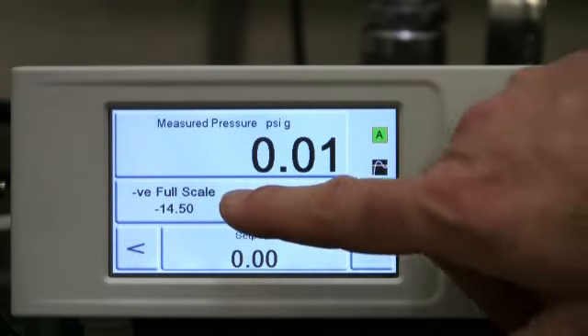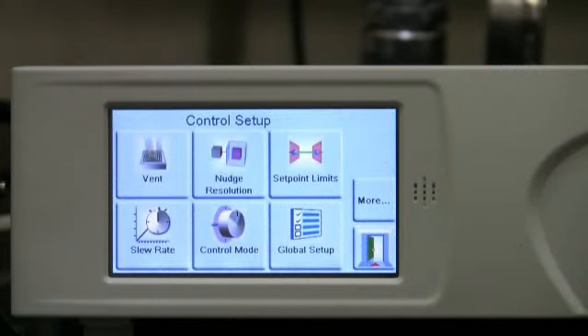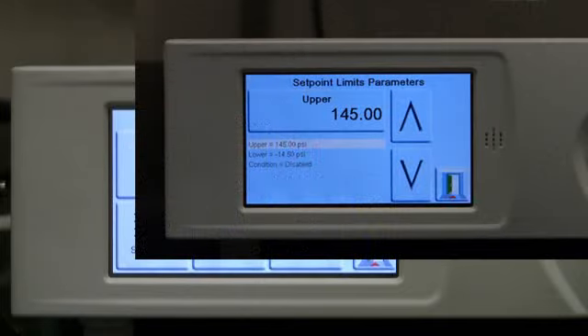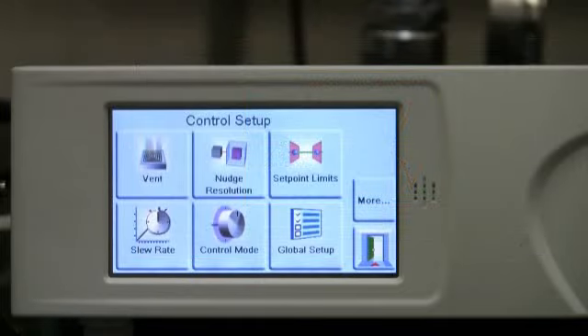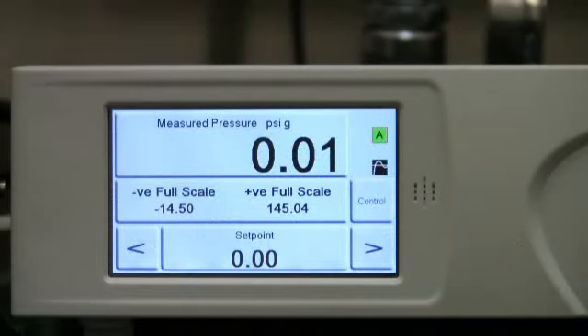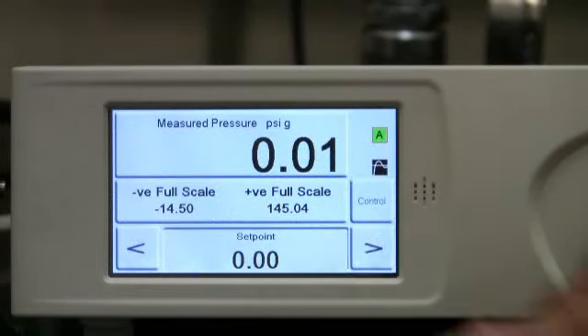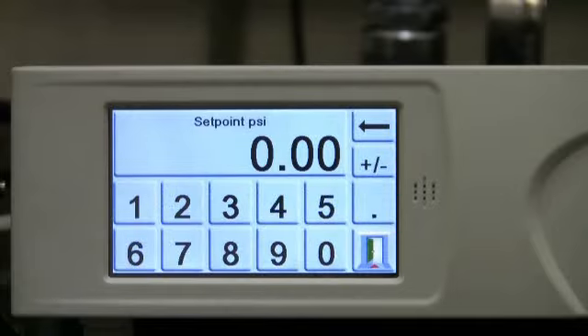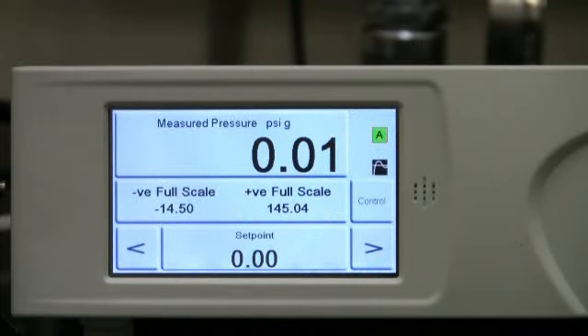The center section is the Control Setup menu. Here, we can vent the test port to atmosphere, select the nudge resolution, change the high and low set point limits, which help protect the device under test, select the control speed parameters, and also access the Global Setup menu. The lower section provides a numeric keypad, which is primarily used to enter the set point pressure. Let's return to the main screen and perform a typical calibration run.